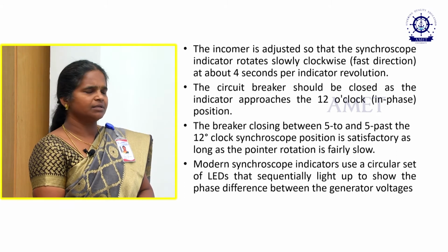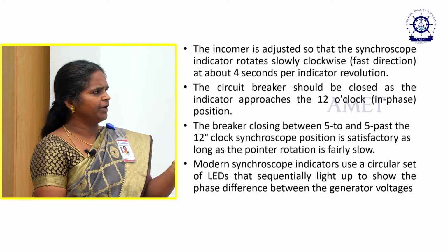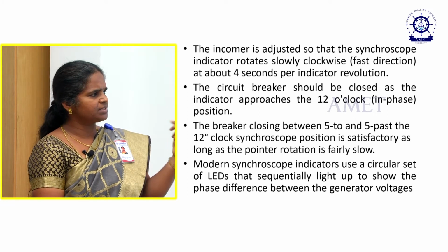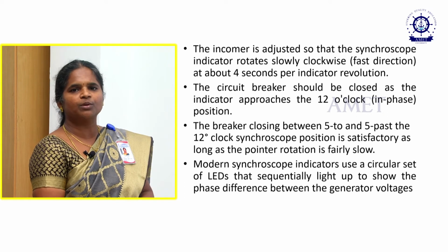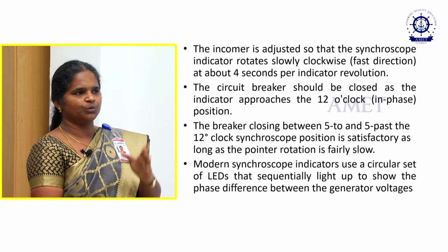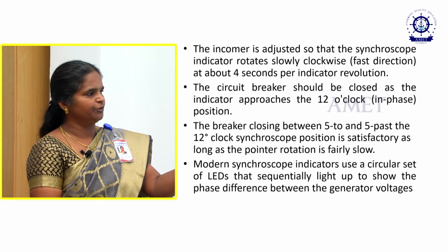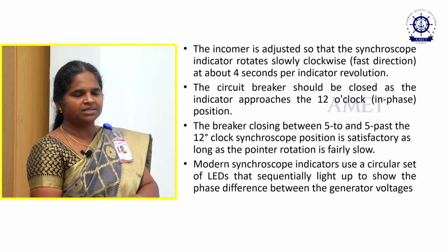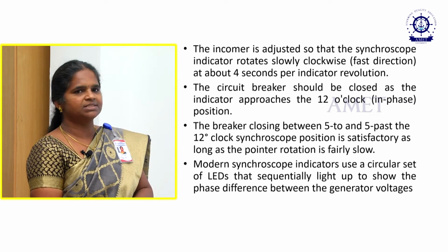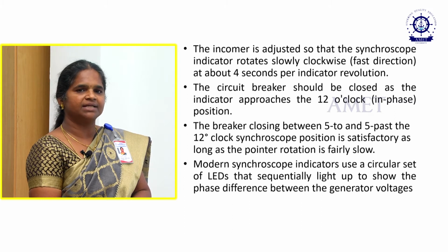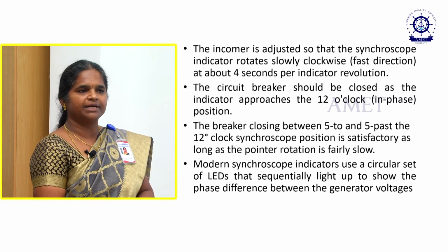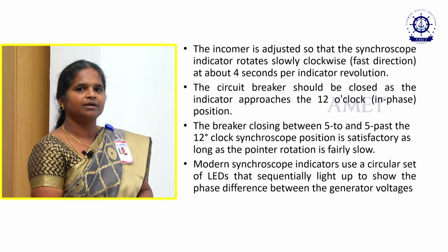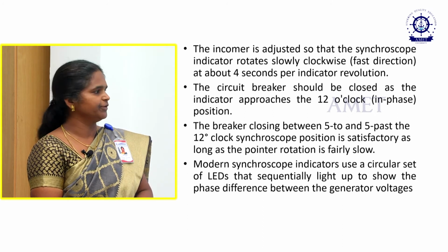The breaker, so apart from the 12 o'clock position, 5 past and 5 to the 12 o'clock position are also acceptable. So, 12 o'clock position, 5 to 12 o'clock, then 5 past 12 o'clock. In these three conditions we can say both the generators are connected in parallel, both running with the same frequency.